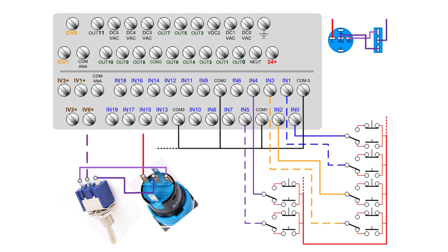So that's what you have here, 4-state inputs. Up in the corner we have an example of the back of the push button, the common, normally open, normally closed, and how it's connected to the toggle switch. So you got plus coming in, it goes through one of those 2 contacts, goes into the toggle switch and then to the actual input on the controller. And down in the lower left, we show the actual components of the toggle switch and the push button switch.